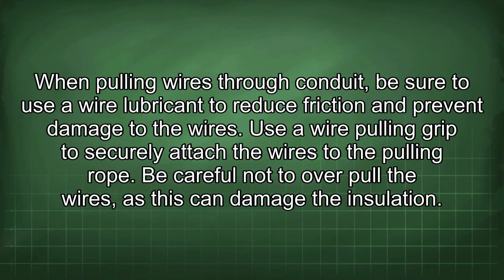When pulling wires through conduit, be sure to use a wire lubricant to reduce friction and prevent damage to the wires. Use a wire pulling grip to securely attach the wires to the pulling rope. Be careful not to over-pull the wires, as this can damage the insulation.